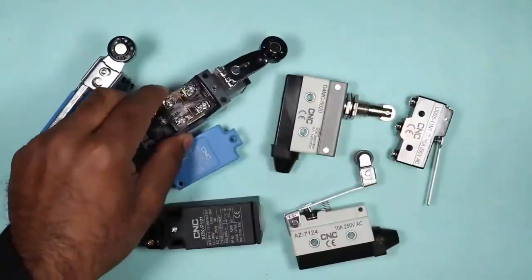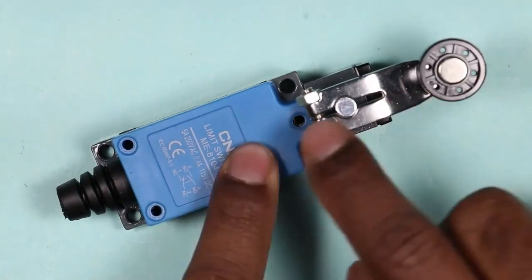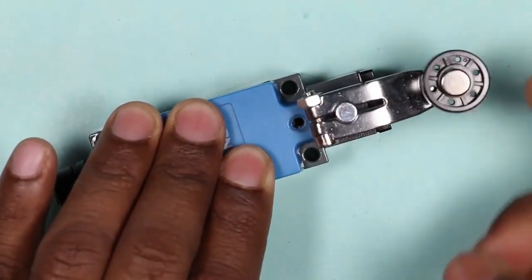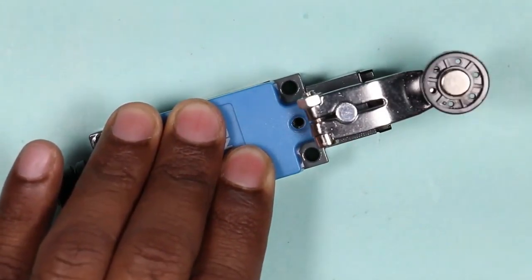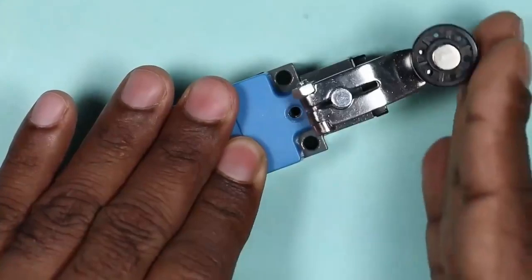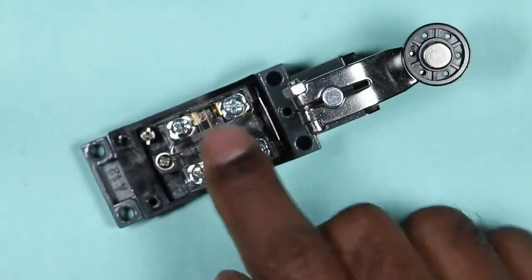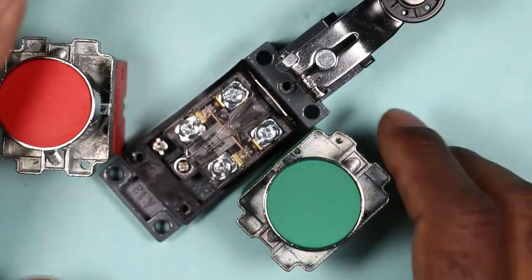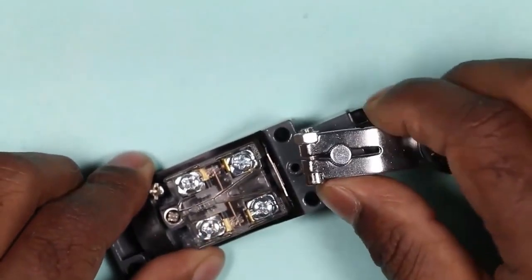Before moving to the wiring part, let's understand some basic knowledge of this limit switch. This part in the limit switch is known as the plunger. On top of the plunger, a roller is given. This roller contacts the moving part and the plunger gets operated. When this plunger operates, then inside the switch an element is present here which is exactly like an NO-NC contact.